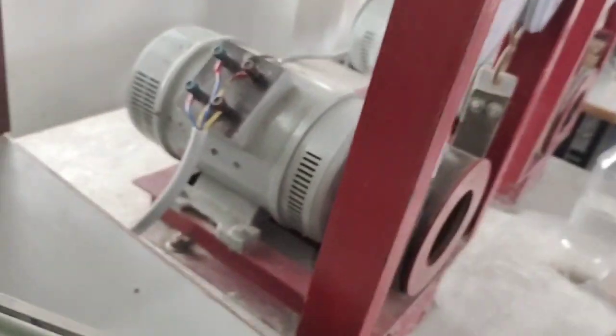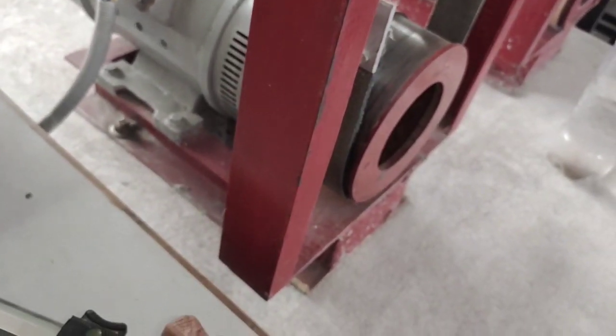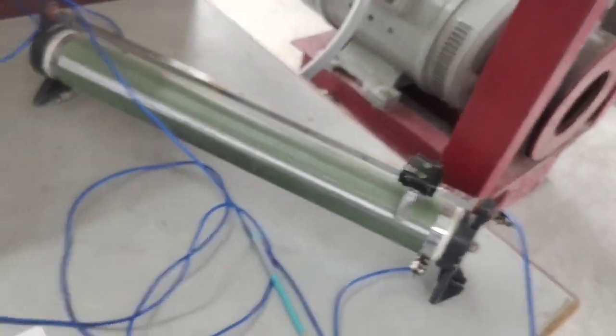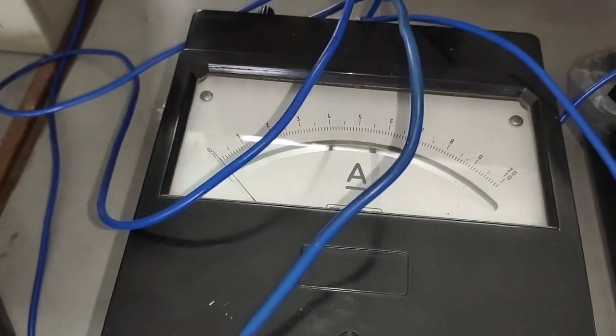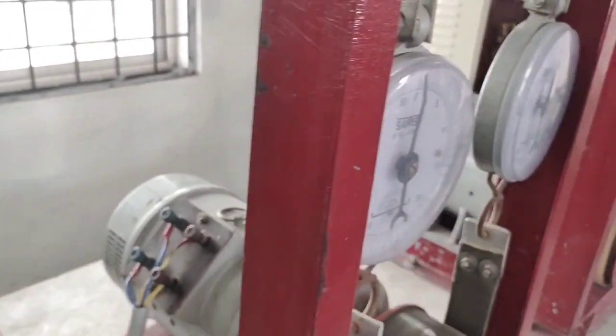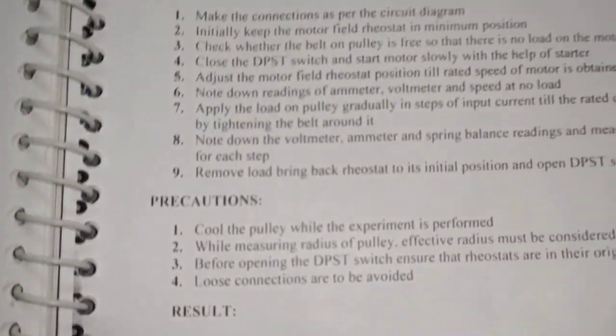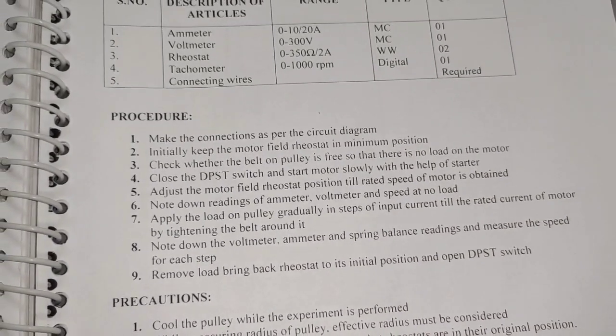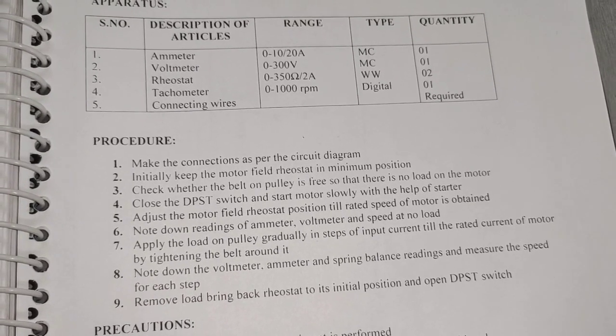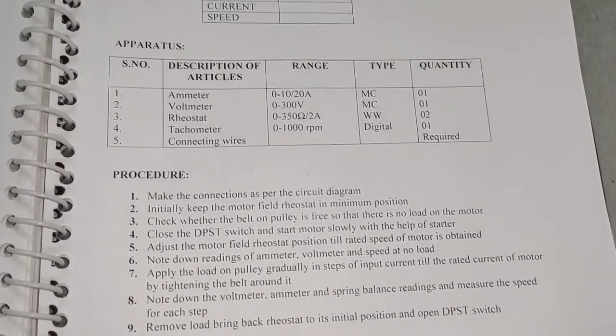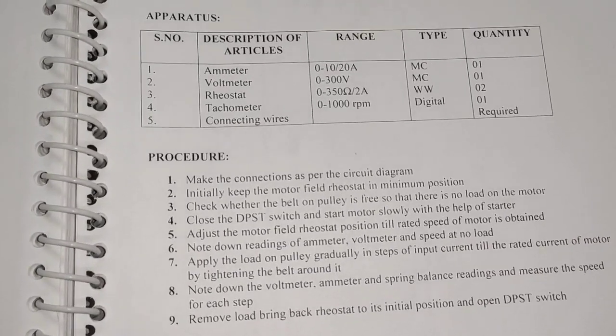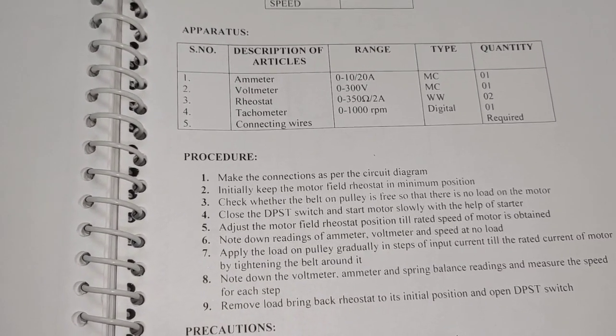Adjust the motor speed by varying the field rheostat position until the rated speed of the motor is obtained — that is 1500 RPM. Then note the readings of the ammeter, voltmeter, S1, and S2 at no load, as the belt is free so there is no load on the motor. Now apply load on the pulley gradually in steps of input current until the rated current of 20 amperes is obtained. For every step, note the values of ammeter, voltmeter, S1, S2, and speed.